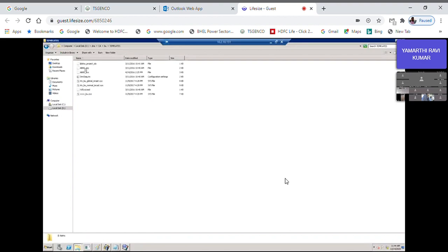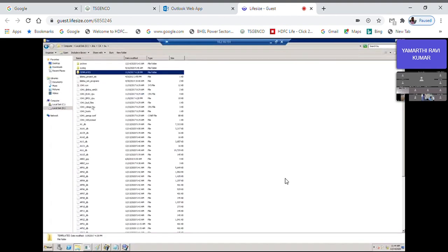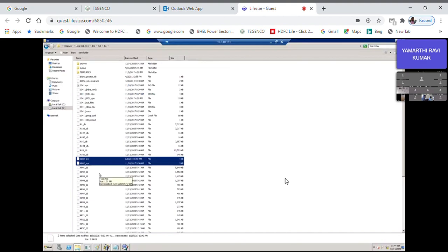There are two important files called the GRP file and the sys file. These two files form all the definitions of that particular plant. So these two we have to copy and put under this location. So these are those two files. If my backup node is AB01, the name has to be AB01 underscore GRP, AB01 underscore sys. If this is AB02, I'll give AB02 underscore GRP and AB02 underscore sys. Now we'll see what to configure in these files. First we'll do the system file.